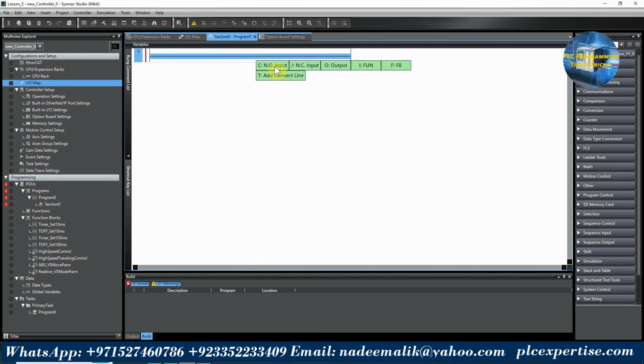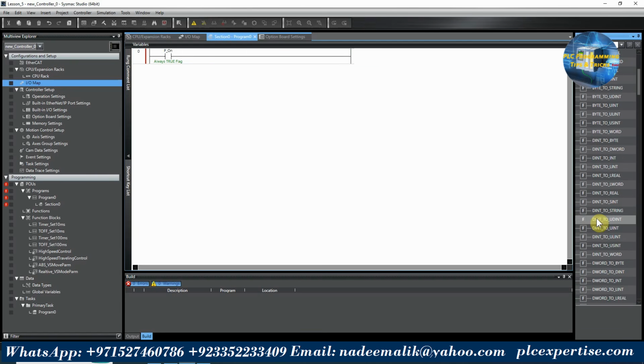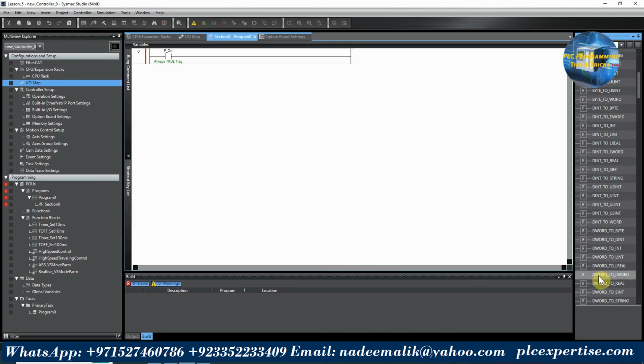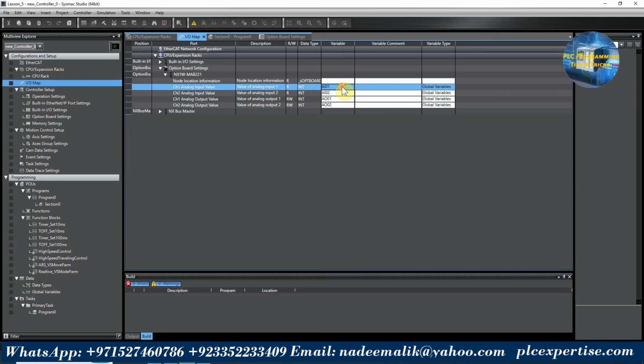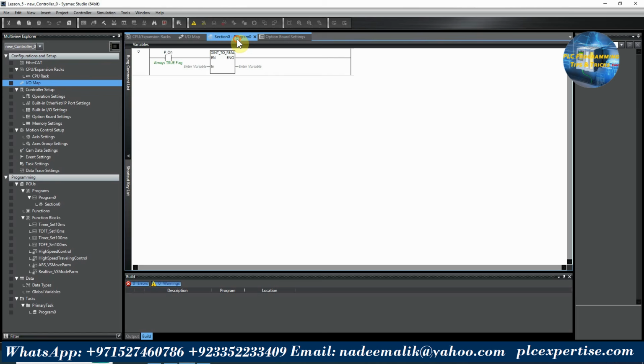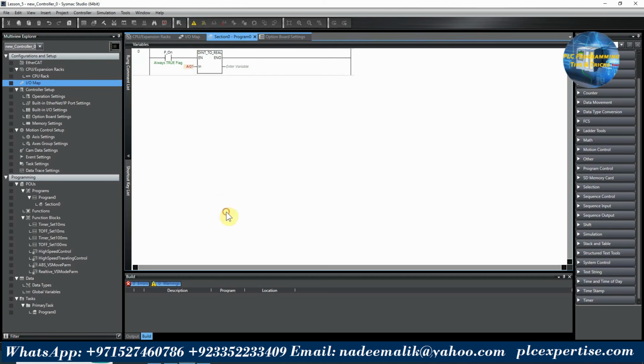First of all, we will create here an NO input, and we will assign here the P_on flag, which is always true whenever the PLC is in the run mode. Next, we have to convert the raw value coming from this pressure transmitter to some real format data. To do this, we will go to the data conversion, and here we will select D into real, double integer to real. And here at the in terminal, we will copy paste this variable AI01.